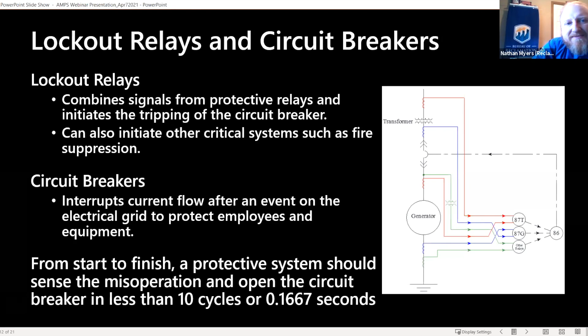When we look at our protection system testing, we see that it can be extremely labor intensive. It's often quite challenging to get to the instrument transformers to be able to perform the necessary tests. It always requires plant equipment to be offline, and some of the maintenance tasks include setting verifications of the protective relays, looking at the CT and PT signals received at the relay, measuring and recording the CT and PT burden measurements, and also verifying that the analog to digital converters at the protective relays or metering is working correctly. All relay calibration and testing information must be maintained in accordance with NERC-WECC to ensure that we're meeting their requirements.